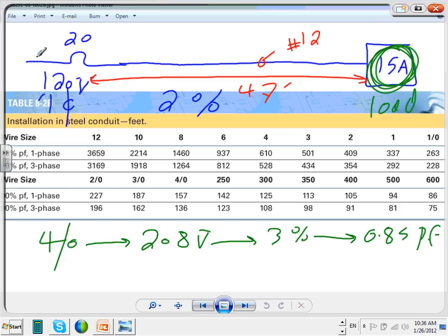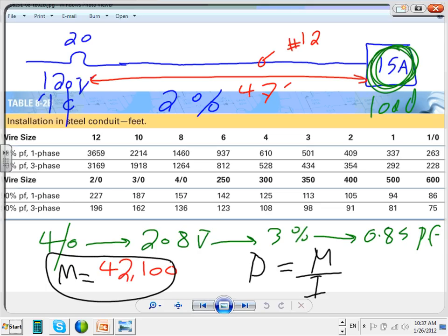Okay, so let's take this number. My number, Chad, from this table is 42100. So what does that mean? Well, here's how you use this one. The distance equals this multiplier divided by the current. D is for the distance, M is for the multiplier, and I is for the current. D is how far I can push that one, based on a 3% voltage drop.